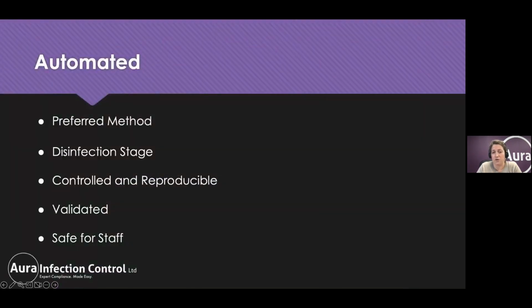The final choice for your cleaning stage would be using an automated process. So using an automated validated washer disinfector is preferable to manual cleaning, because it includes a disinfection stage that renders instruments safe for handling and inspection. And it's the preferred method for cleaning dental instruments because it offers the best control and reproducibility of cleaning, and it's a process that can be validated.